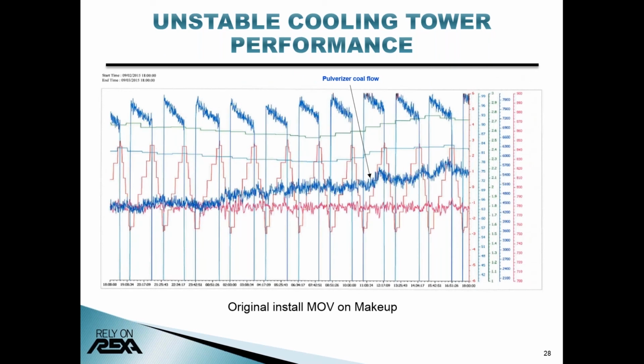This next graph shows a trend in blue in the middle of the page, laid on top of the previous graph. Can you explain what this new trend line shows us? Sure. The new trend line on here is our fuel flow into the pulverizers, our pulverizer coal flow. As you can see through the day, the coal flow continues to ratchet up all day long. This was a 37,000 pound increase in coal flow throughout the day.